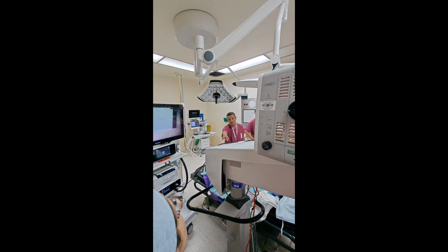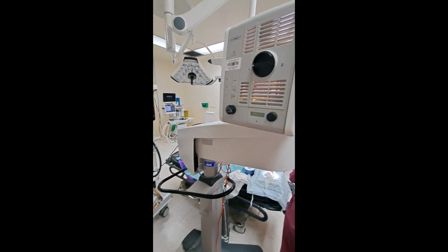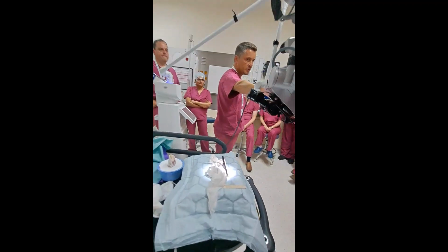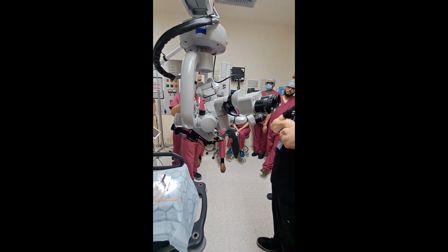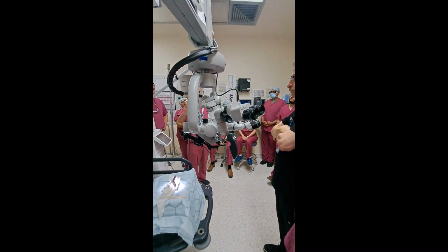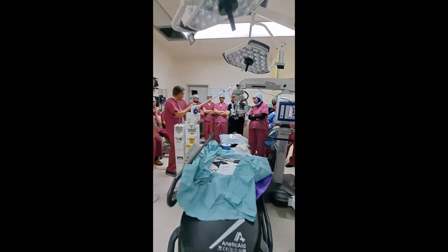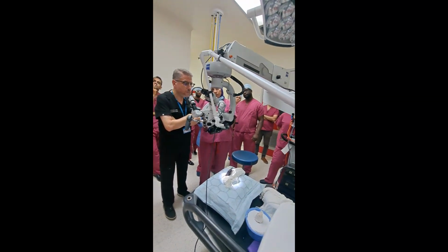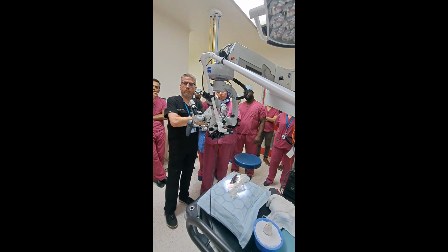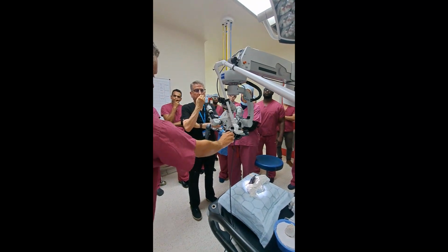The focal distance is displayed on the microscope here at 400. There is also this yellow button here on the Zeiss microscopes that will freeze your working distance. So it's a good idea to set those things to 400 and this to 0 and 400 on this red dot, and then you know where you are. You're then just trying to zoom out and find where that beam is nicely focused. The other way of doing it is you can have a random focal distance and then make some adjustments.